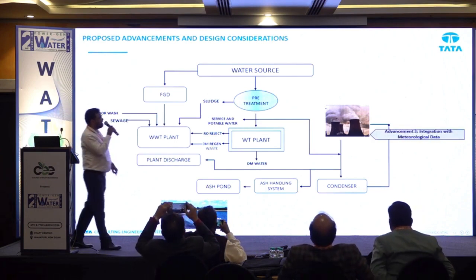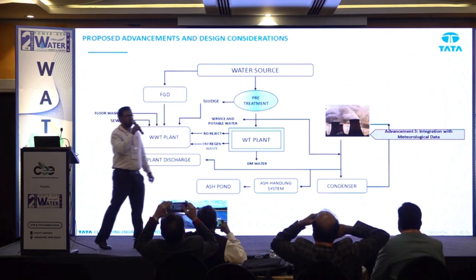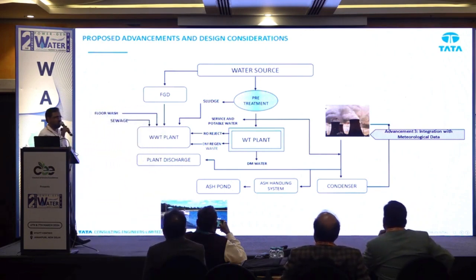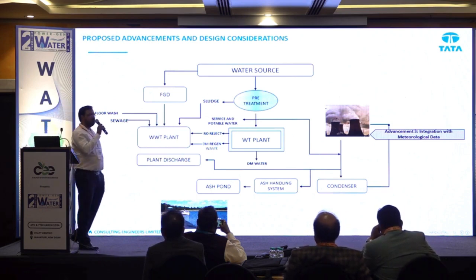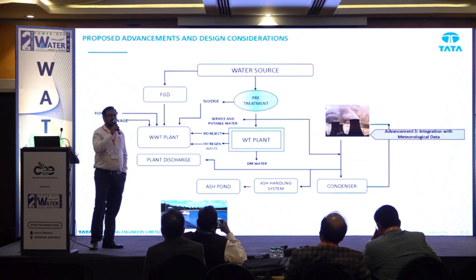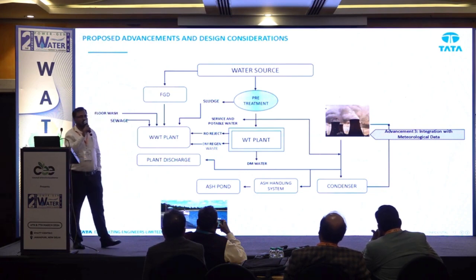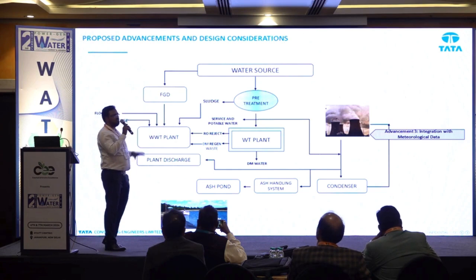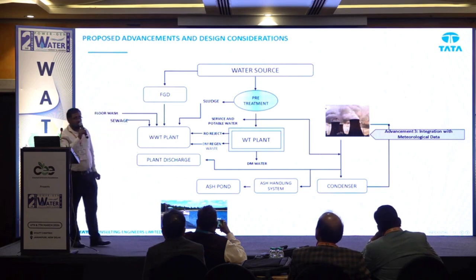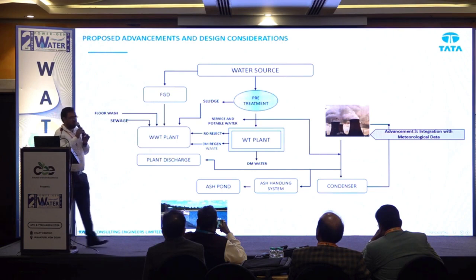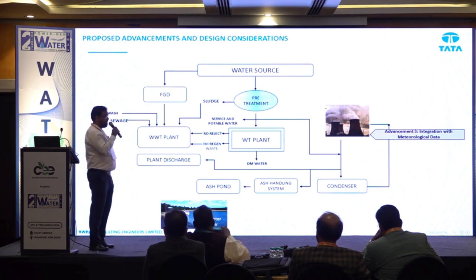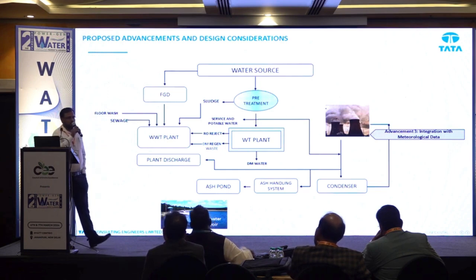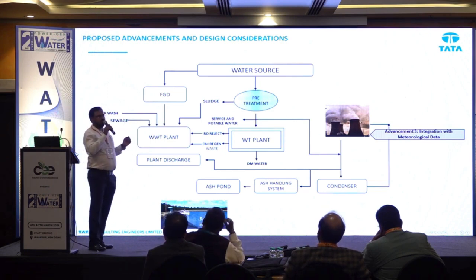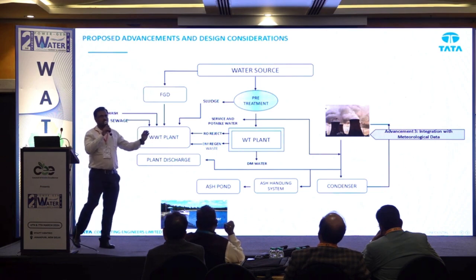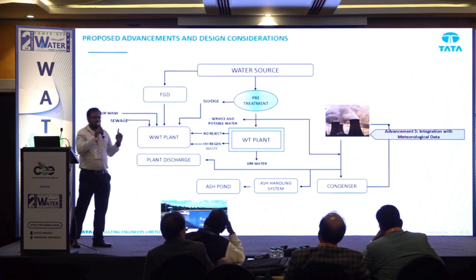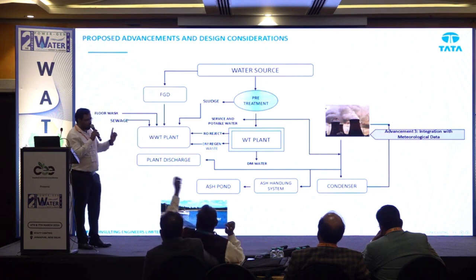So coming now to the third one. This is the third advancement, the integration with meteorological data. How? The cooling tower system is operated in a conventional way, where our fan rotates at a particular RPM day and night. Nobody is watching. Sometimes it may be modulated. But based on artificial intelligence and other advancements, it is now possible to collect meteorological data like wet bulb temperature, dry bulb temperature and relative humidity.